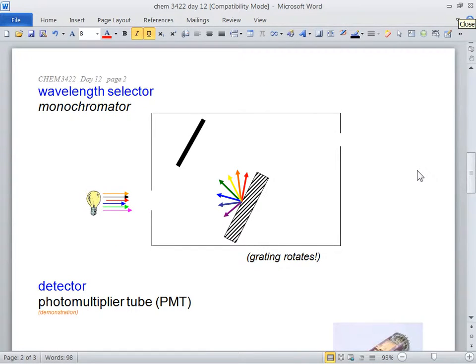Okay, so we had our light source. Now we have our what selector? Wavelength selector. So the one that we're going to worry about is a monochromator. So just have an idea how this works. Now, when you were on the AA, you messed with something called slit widths. Remember that, Andy? Slit widths. Or not? Does anyone remember this? Yeah. And then you had to look in the AA cookbook, and it told you, oh, use this wavelength, and use these slit widths and stuff. Okay, here's a monochromator. Slit widths are in here somewhere.